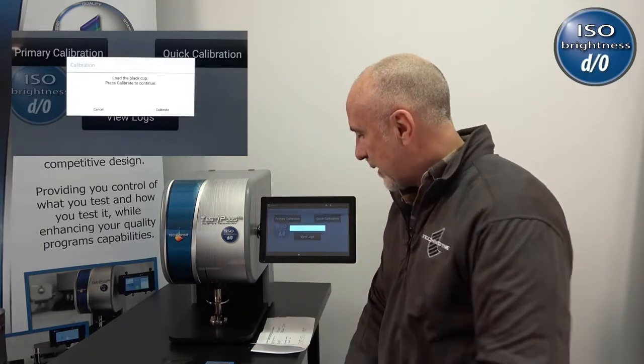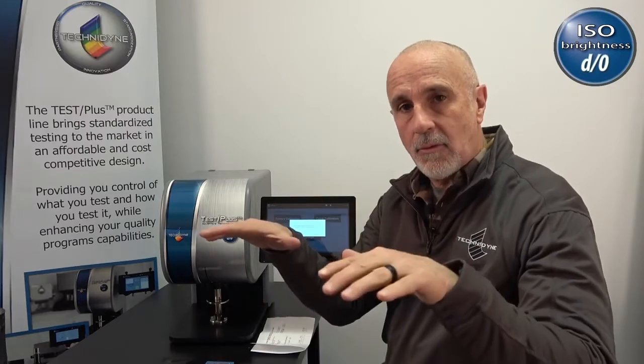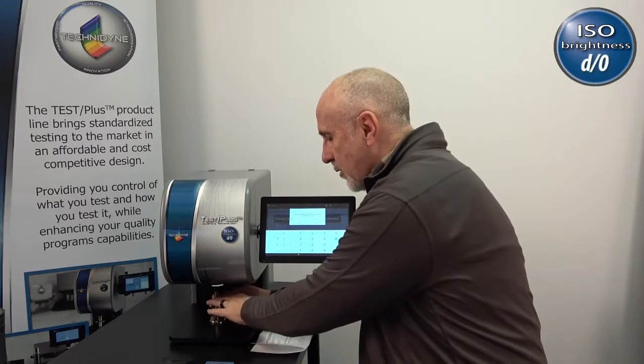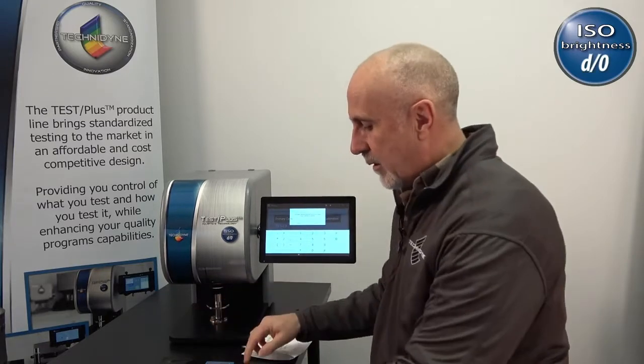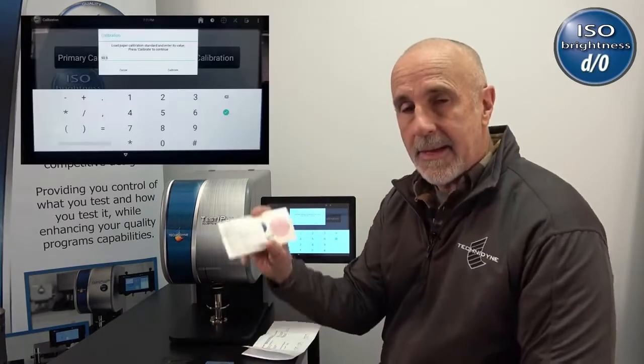So the first thing you're going to need to do is load the black cup, which we've already done, and hit calibrate. So I touch calibrate. That sets the low light level reading, the 0 reading in the instrument. Okay. Next thing it's going to do, it's going to tell me to load the 90 non-fluorescent standard.